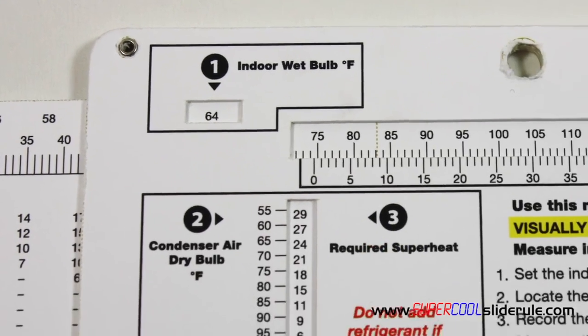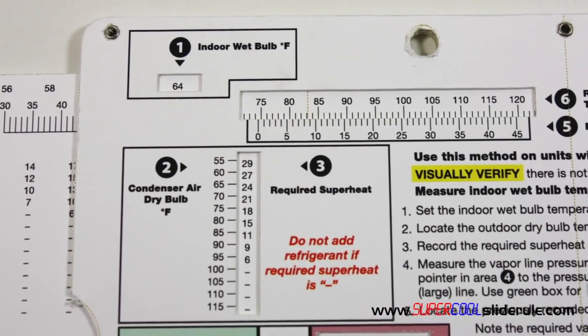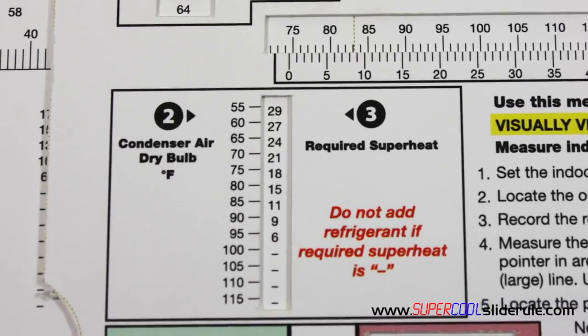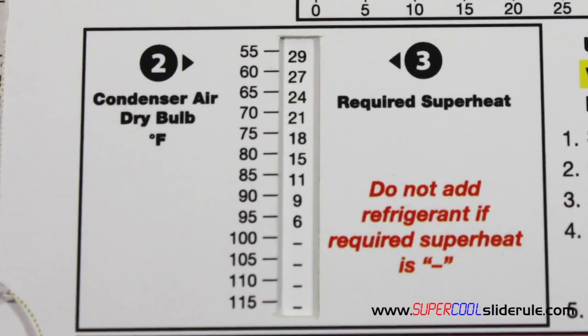Next, obtain the outdoor dry bulb temperature and locate that temperature here in area 2. We will record the required superheat temperature directly to the right of the outdoor temperature. In this example, our outdoor temperature will be 90 degrees, so our required superheat is 9 degrees.